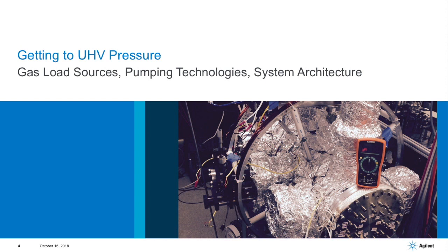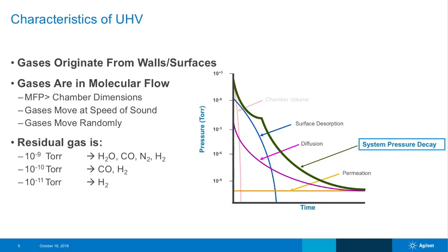Let's talk about how we get to UHV pressures — some gas load sources, some of the pumping technologies available, and a little bit on the architecture of a typical UHV system. In UHV, we're talking about gases coming off walls and surfaces, so we're really not that concerned with the chamber volume, only in the way that impacts the internal surfaces. We need some sort of baking, which is the best mechanism we have today for driving off molecules — typically water — off the surface, and we can then get to the true nature of a UHV system.